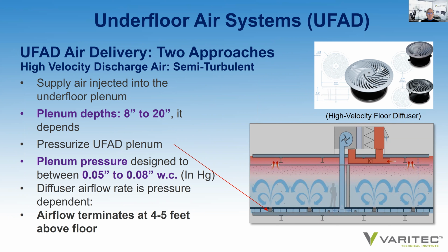Supply air is injected into the underfloor plenum. Plenum depths are about 8 inches to 20 inches. In the past, when I was promoting underfloor back in 2010, 2012, we would have to design to 16-inch plenum heights because we had fan terminal units under the floor that I'll illustrate shortly. That is no longer necessary with the newer technologies that are available, and again, we'll demonstrate why here shortly.